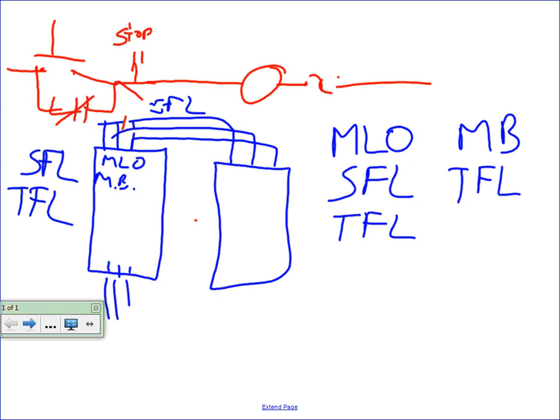If you have, like on your project, a main distribution panel, 500 amp, feeding other panels downstream at 208, you can get away with using a main lug only panel on those downstream devices, okay? If the service was 480 volt, and you're using a transformer to transform it down to 208, then at that point, that panel has to have a main overcurrent device.